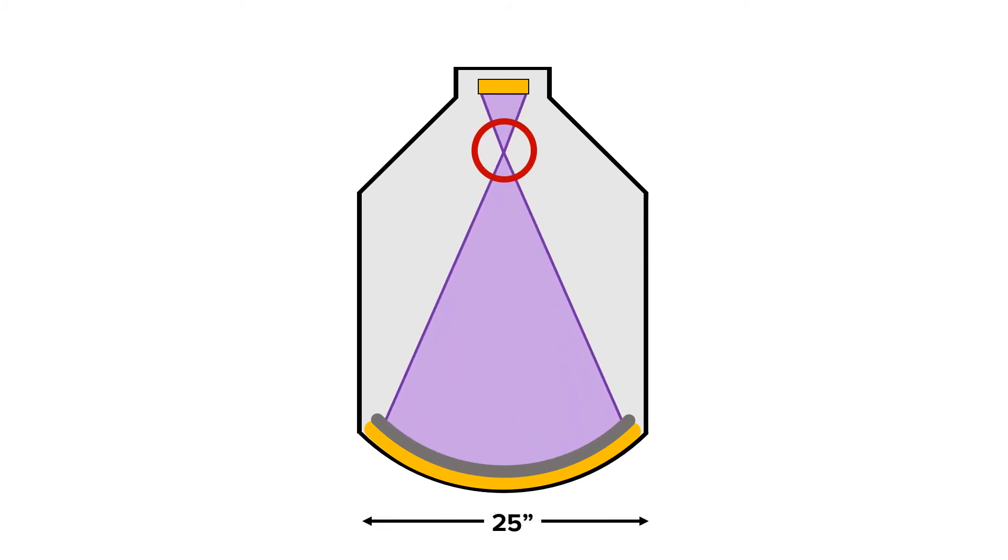The focal spot is closer to the output phosphor when we're using a larger field of view versus when we magnify. That focal spot is going to get further away from the output phosphor. When we go from a 25-centimeter to a 17-centimeter, we increase the voltage across the intensifier. Increasing voltage reduces the field of view and magnifies the image.